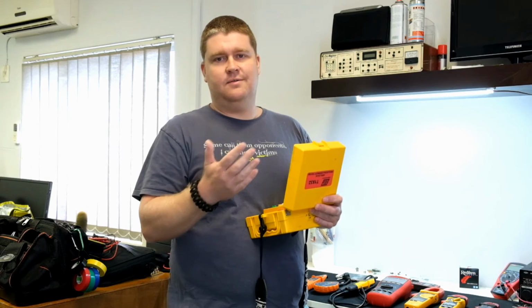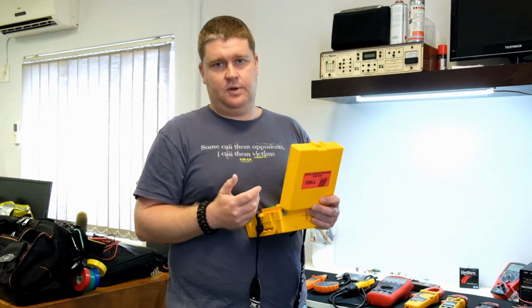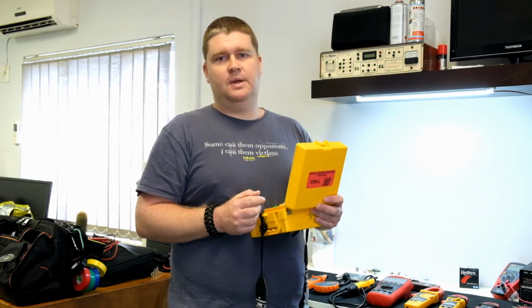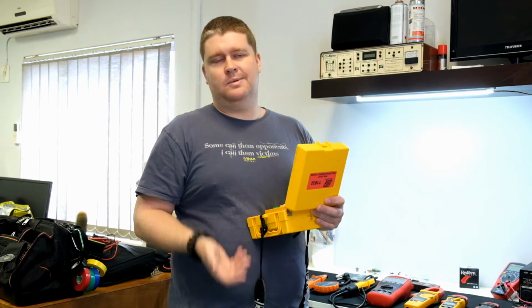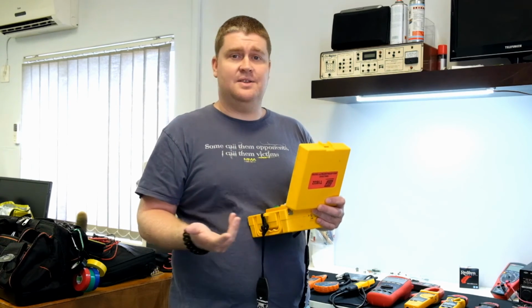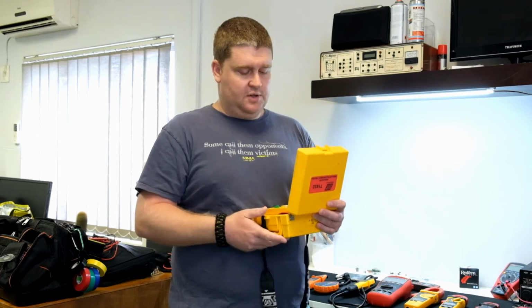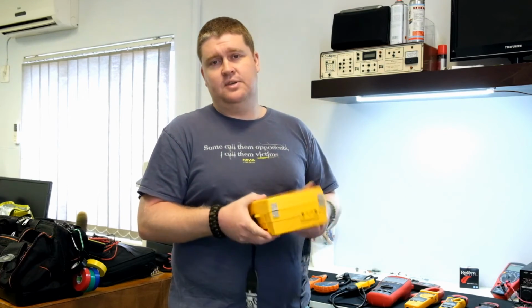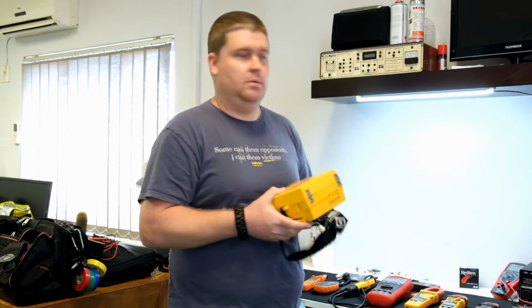So at 1000 volts, 10 mega ohms for example, insulation should be good. If it goes below a certain level, say 2 mega ohms or something like that, then the insulation is not good. Then you need to start checking why, and there's a potential for an accident or fire or whatever the case may be.